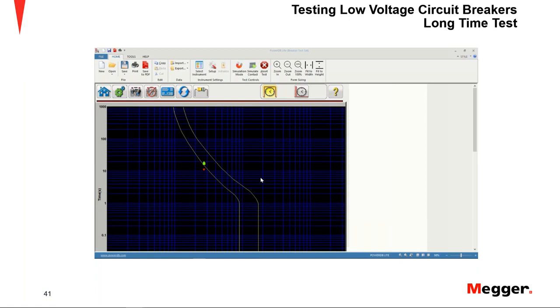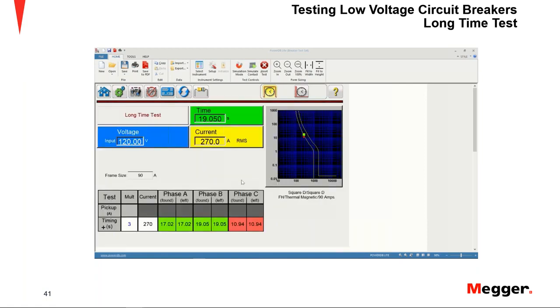And let's say that, okay, our phase C failed. So let's say we change the settings or we do some maintenance on the breaker, and notice that there is an as left column, as found and as left, right? So I can rerun my test on the as left, after I did either some maintenance procedures, corrections, or change the settings of the circuit breaker. And I will be able to retest that phase while keeping my as found result, in this case a failed result. It's important to have that in the report.